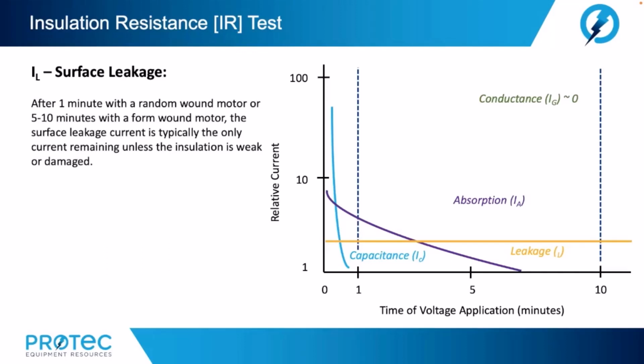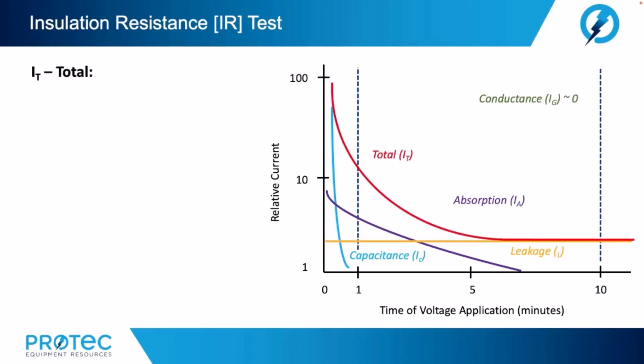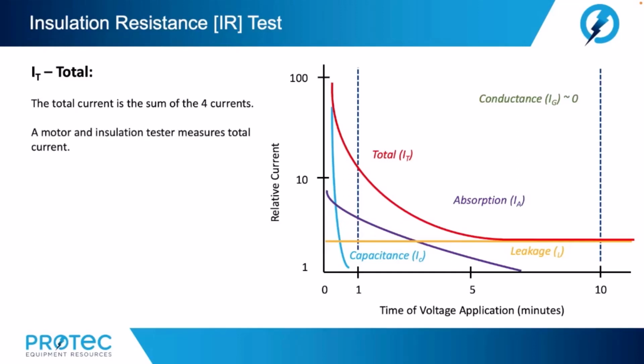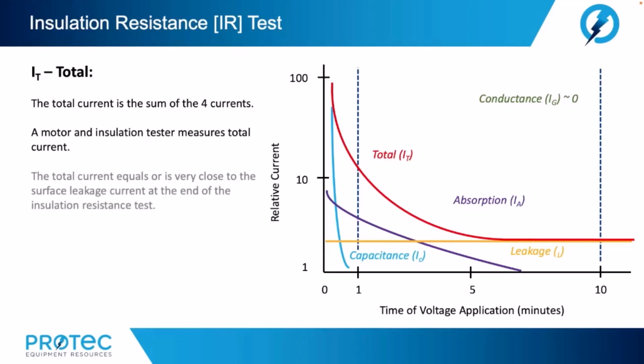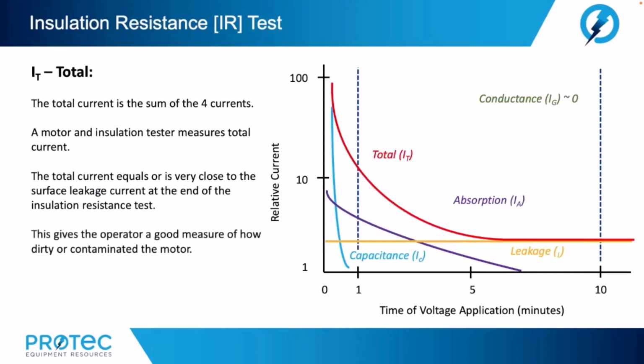Now, after 1 minute with a random wound motor or 5 to 10 minutes with a form wound motor, the surface leakage current is typically the only current remaining unless the insulation is weak or damaged. And that brings us to the total current. The total current is the sum of the four currents. A motor and insulation tester measures total current. The total current equals or is very close to the surface leakage current at the end of the insulation resistance test. This gives the operator a good measure of how dirty or contaminated the motor is. It also alerts the operator to a possible catastrophic connection from the windings to ground.